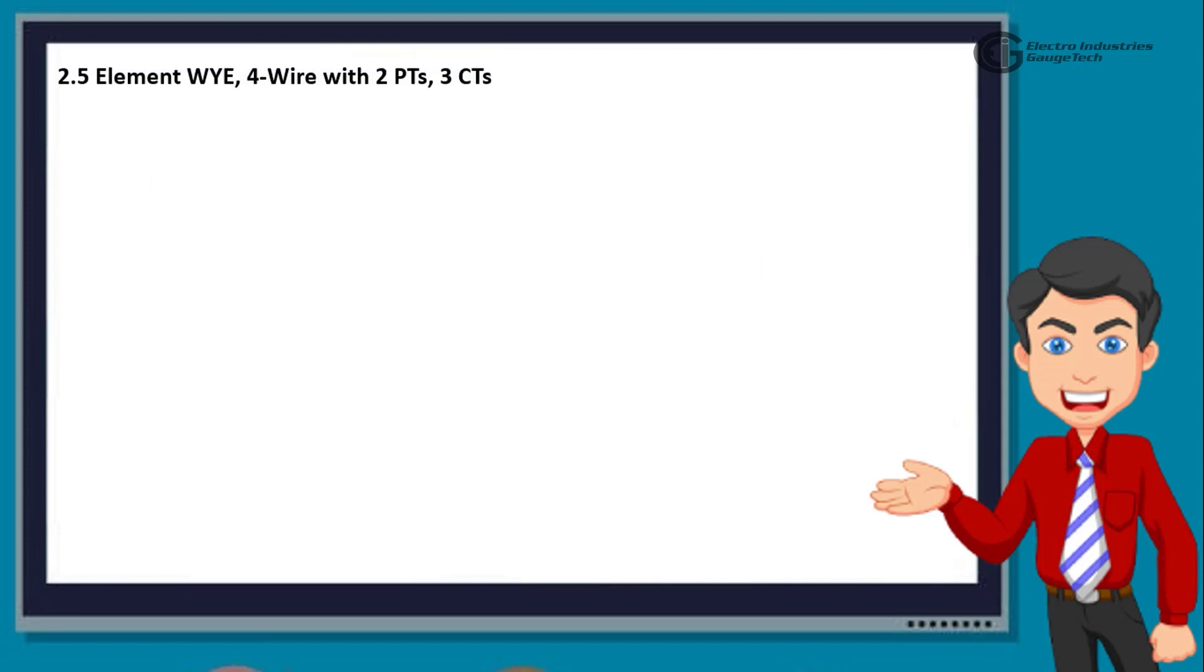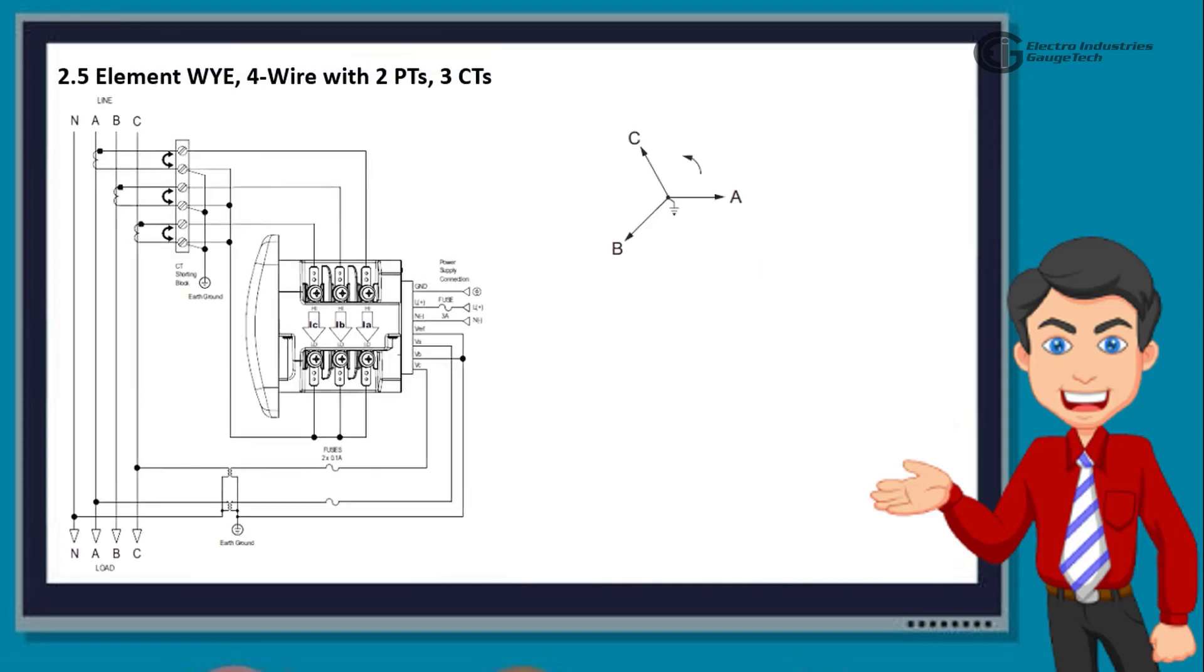Another one is 2.5 element Y, 4 wire with 2 PTs, 3 CTs. This wiring diagram shows 3 phase, 4 wire system Y with PTs, and 2.5 element. When using this wiring, select 2.5 L Y from the Shark Meter's front panel display.